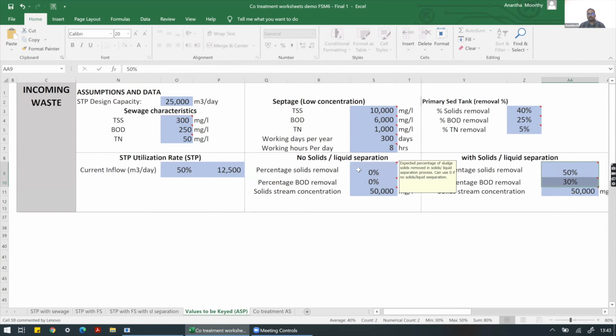Each technology provides a particular level of solid liquid separation and solids removal, and it also helps in reducing BOD to a certain level, because when organic particulates are removed, a certain level of BOD is also removed with the solids. That reduces the organic load on the liquid stream, which has to be co-treated in the secondary modules.